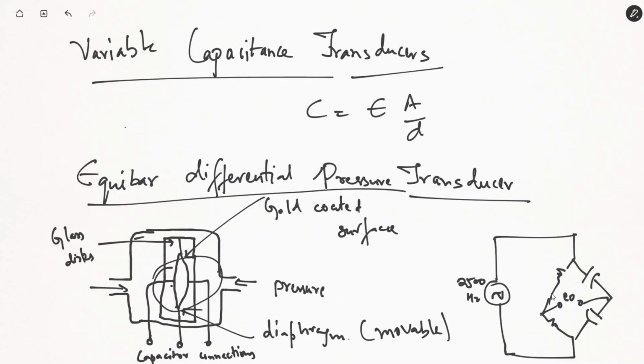But if the pressure from both sides is equal, if equal pressure is being applied from both sides, that will result in a capacitance that would balance this particular bridge, that would make sure your output voltage is zero. So this equibar differential pressure transducer works on the principle of a capacitance transducer.